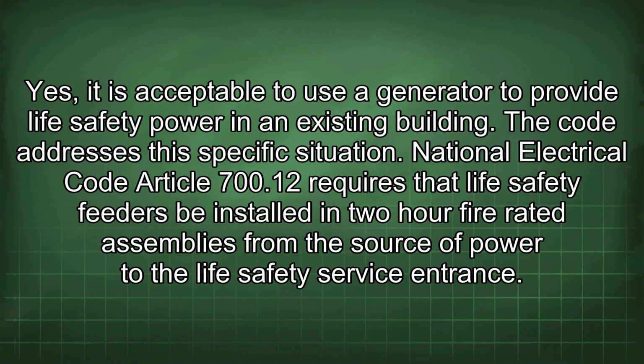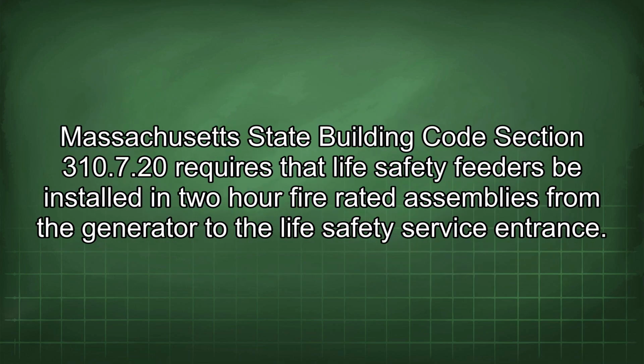Yes, it is acceptable to use a generator to provide life safety power in an existing building. The code addresses the specific situation. National Electrical Code Article 700.12 requires that life safety feeders be installed in 2-hour fire-rated assemblies from the source of power to the life safety service entrance. Massachusetts State Building Code Section 310.7.20 requires that life safety feeders be installed in 2-hour fire-rated assemblies from the generator to the life safety service entrance.